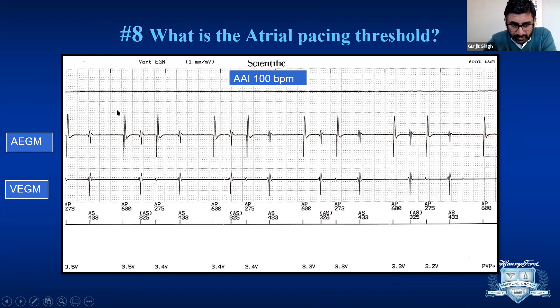And the reason it's not happening is because the pacemaker is sensing something. Because remember, you are pacing in AAI mode. If you see something, you are not going to pace. So this is an example showing you the far field signal, again, crosstalk from the ventricular being sensed on the atrial channel. And that's the reason you cannot complete your threshold testing. So to complete this threshold testing, what would you do?